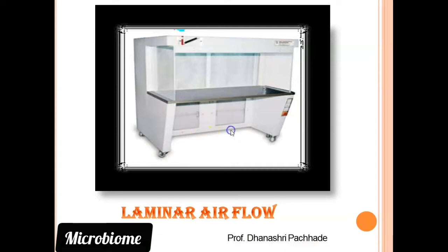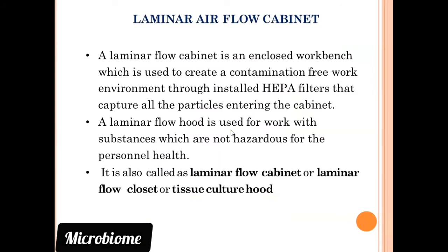So first of all, we will see what is meant by laminar airflow cabinet. A laminar airflow cabinet is an enclosed workbench which is used to create a contamination-free work environment through installed HEPA filters, that is high efficiency particulate air filters, that capture all the particles entering the cabinet. A laminar flow hood is used to work with substances which are not hazardous for personal health. It is also called laminar flow cabinet, laminar flow closet, or tissue culture hood.